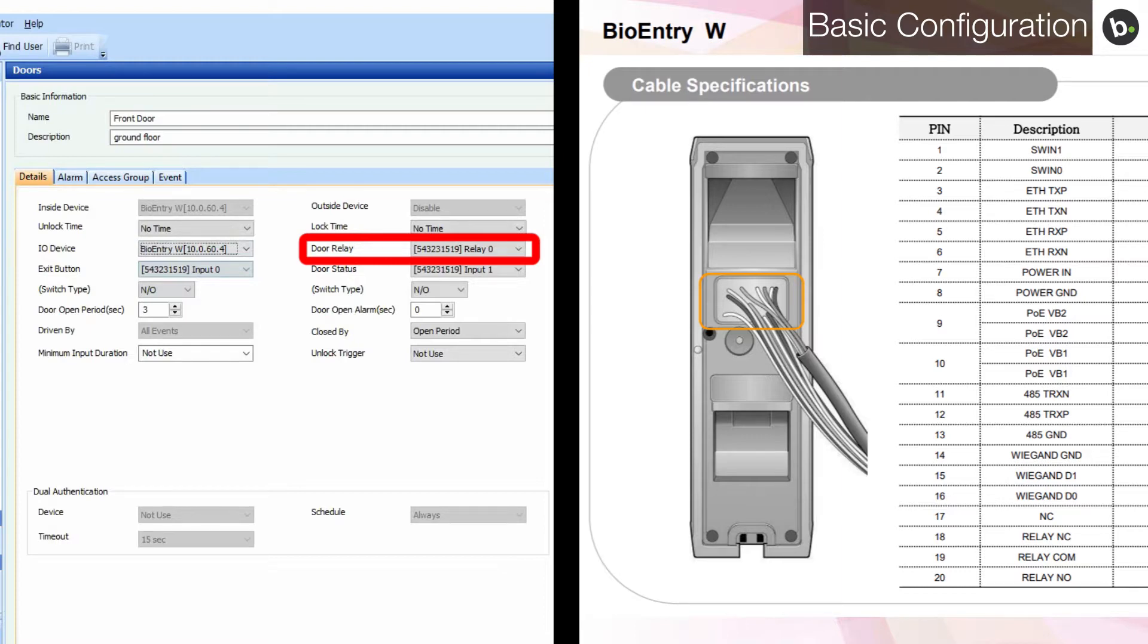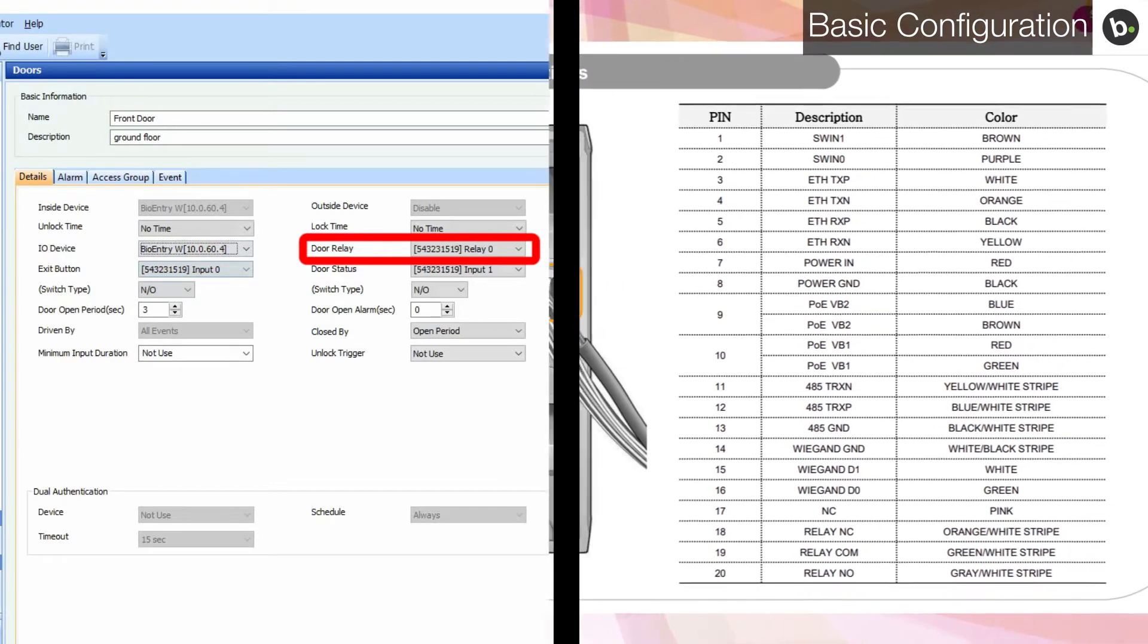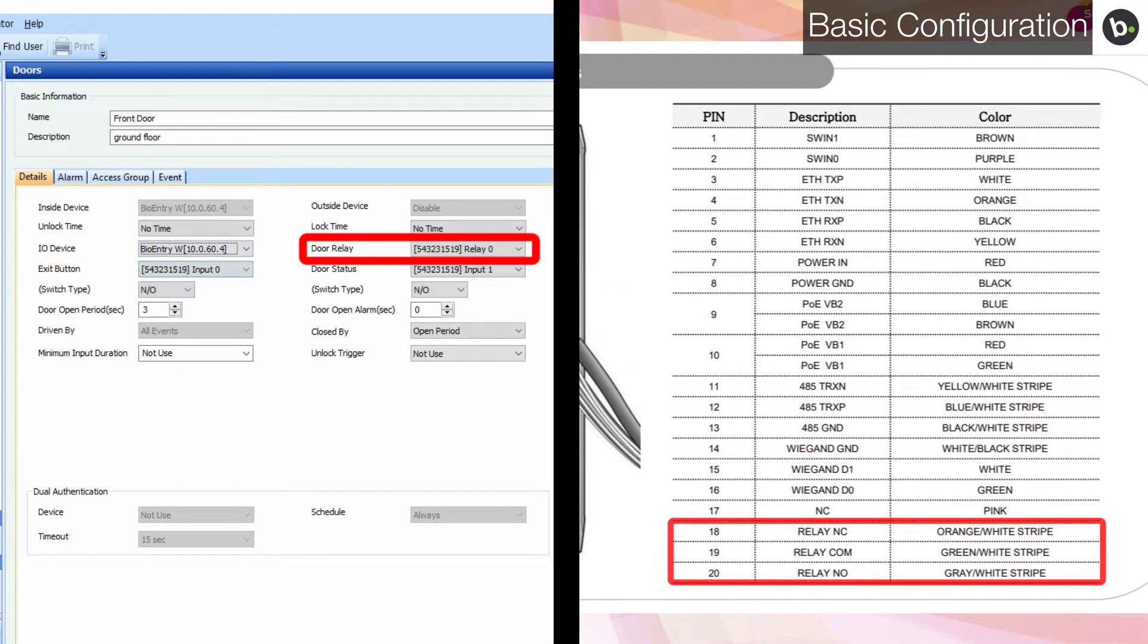For example, since I am using a bio-entry W, I will use the green wire with white stripes and either the orange wire with white stripes, or the gray wire with white stripes, based on my type of maglock or strike.